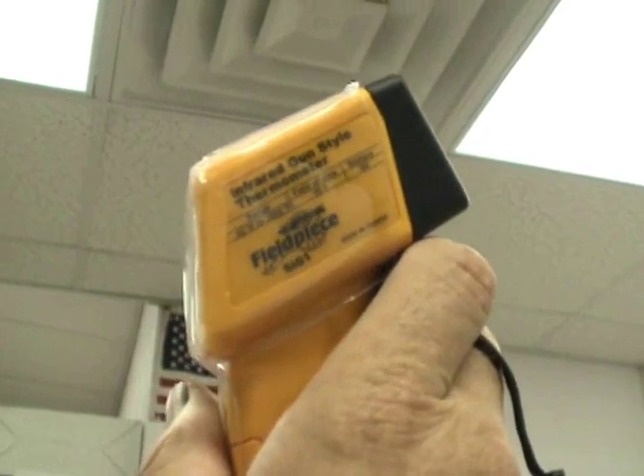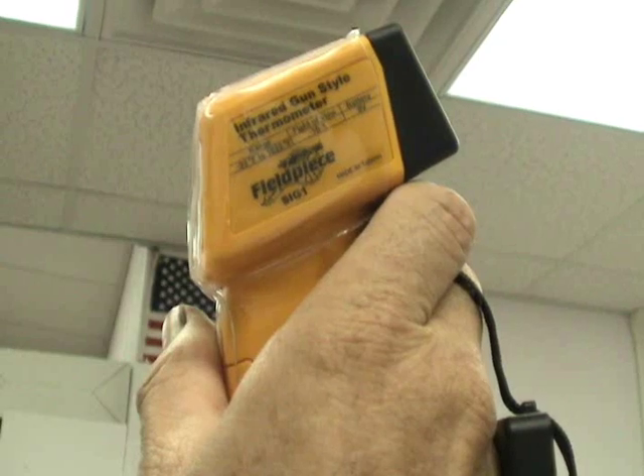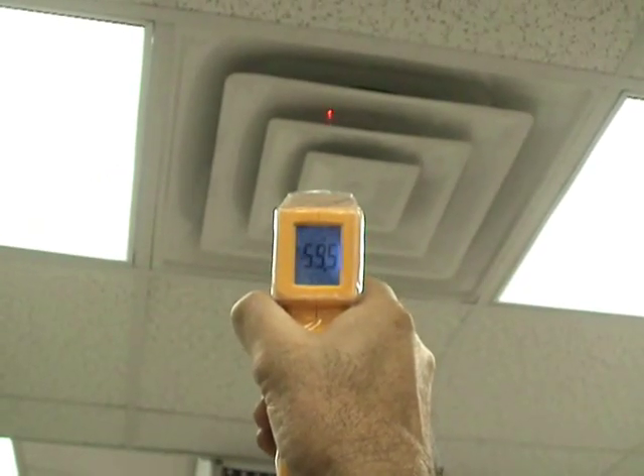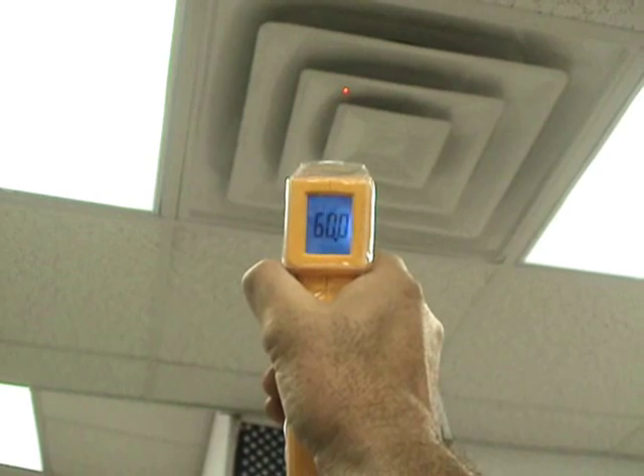First, we'll shoot the supply grill with the laser thermometer — this is the Fieldpiece SIG1, and it's a pretty decent laser thermometer. We're getting 59.5 to 60 degrees on the supply grill. Then we walk over to our return grill and shoot that, and we compare the difference in temperature.